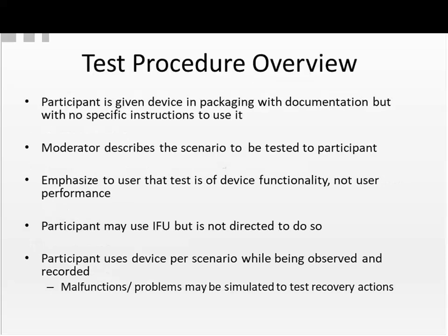An overview of the actual test procedure. The participant is given the device in its packaging with its documentation, but with no specific instructions to use the documentation. The moderator describes the scenario to be tested to the participant.